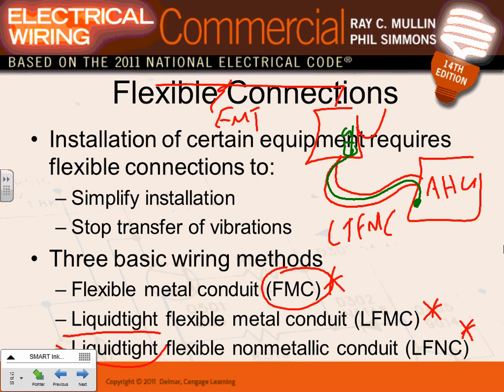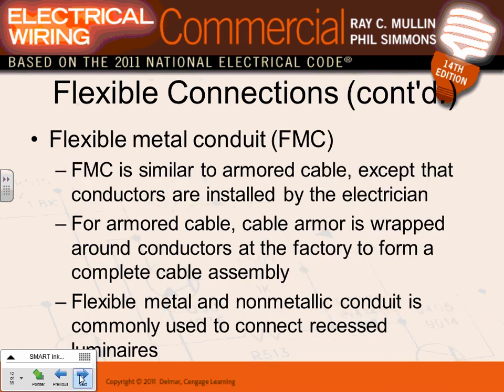That's your flexible conduit - use it to tie to equipment, whether fixtures or mechanical equipment. A couple of things about flexible metallic conduit: it looks like MC cable without conductors inside it. You put conductors in it and it effectively becomes MC cable. Flexible metallic conduit is commonly used to connect recessed lighting fixtures and mechanical equipment.